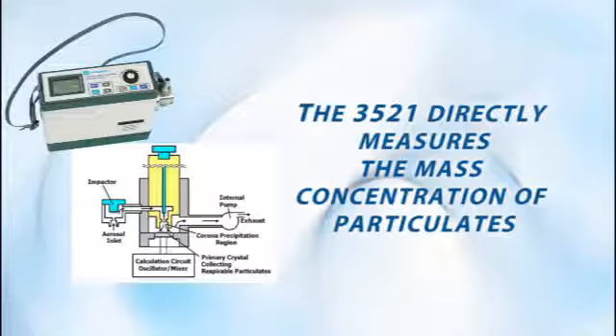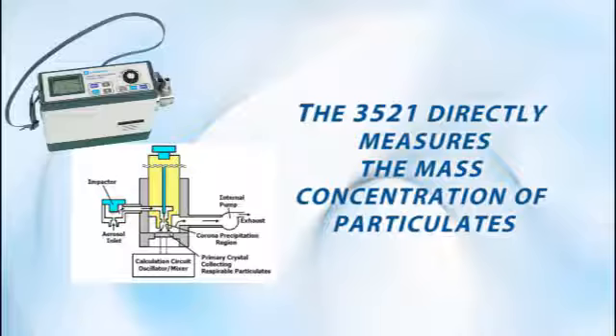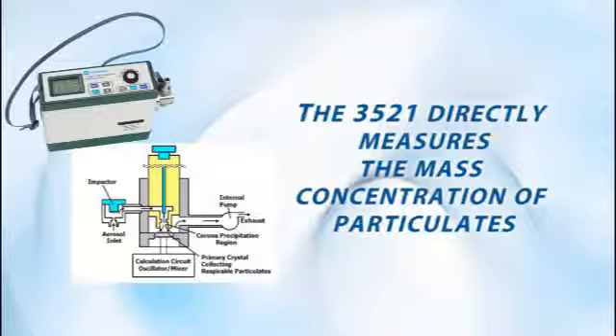The 3521 collects particulates from the air and deposits them on a charged piezo crystal. The frequency of the crystal changes, and based on that change, the 3521 can tell you the mass of the measured particles. There's no need to use a k-factor to account for density.